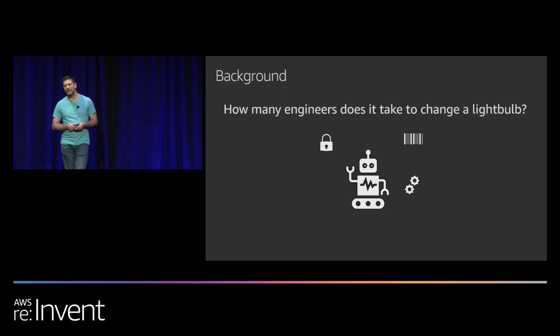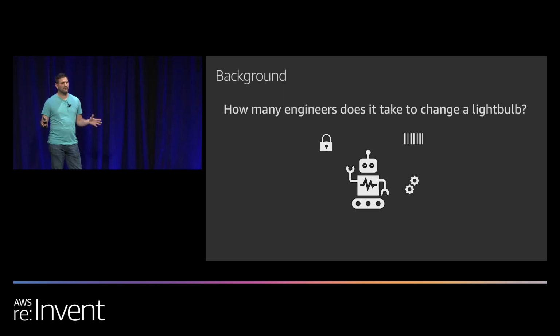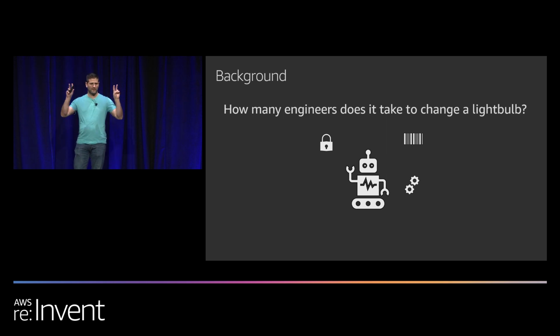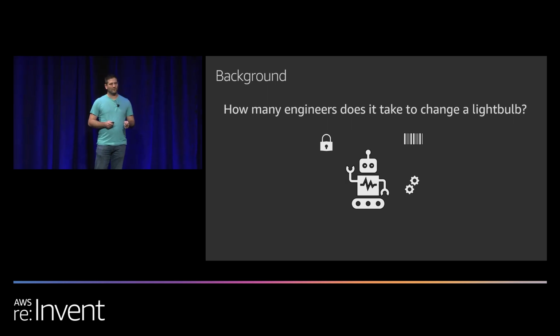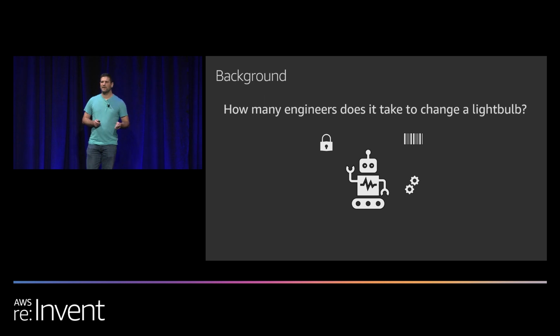And one of the problems that we were having was, I would venture to say that we had probably 10 or more versions of code running on our PLC across the network at any given time. We would do an update with a controls engineer on site, and then we would take that update and roll it out across the network. That process would include another controls engineer flying around the country, deploying it somewhere, possibly identifying a new bug because the environment is slightly different.